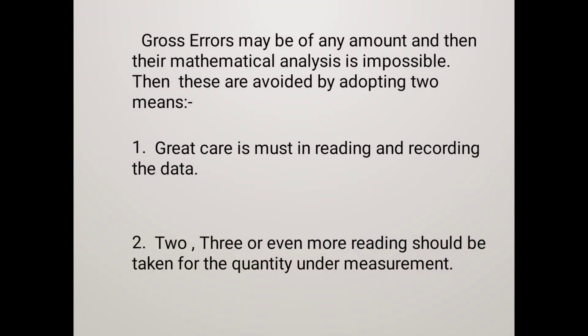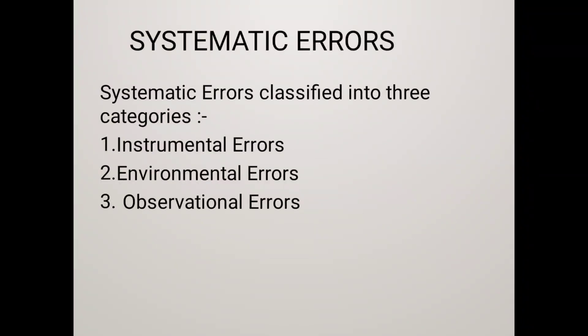Next is Systematic Error. Systematic Errors mainly result from the shortcomings of the instrument and the characteristics of the material used, such as defective or worn parts, aging effects, and environmental effects. A constant uniform deviation in the operation of an instrument is known as Systematic Error. It is classified into three types: Instrumental Error, Environmental Error, and Observational Error.